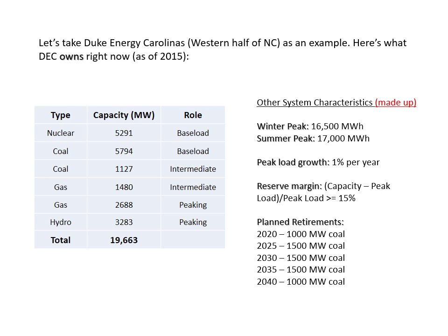And remember, we've talked about the need to provide spinning and non-spinning reserves in electric power systems, and the rule of thumb for doing that is this N-1 criteria. So you have to provide enough reserves to meet the largest single contingency in your system, which is usually a nuclear power plant. So if there's a nuclear power plant that's 2,500 megawatts, Duke at all times has to have backup capacity available to meet a sudden increase in demand of 2,500 megawatts or a sudden decrease of supply of that same amount.